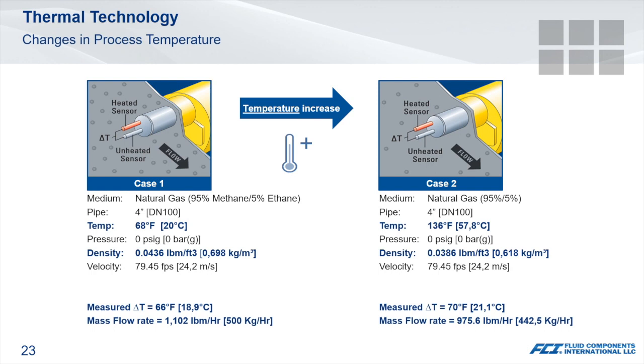Changes in temperature will have the opposite effect on gas density. Also, changes in the process temperature will not impact the gas density as much as changes in pressure. The only difference in process conditions between case 1 and case 2 is an increase in temperature. Increased temperatures result in fewer molecules cooling the heated RTD. Doubling the temperature only reduces the mass flow by 11.5%. Inversely, decreasing temperatures will result in higher mass flow as the gas becomes denser.